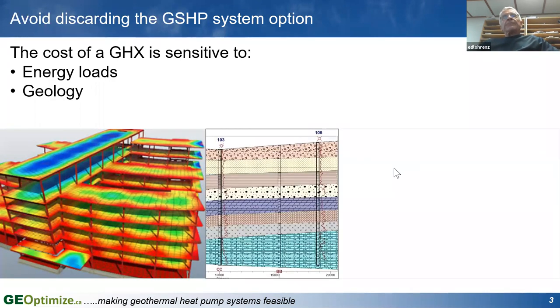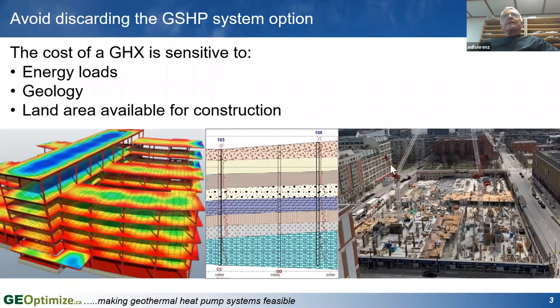The other thing that has a big impact is the geology that you're dealing with. If you're working with clay, that has a certain thermal conductivity, certain thermal properties that may limit how much heat you can put into it, which means you need to put more pipe in the ground. If you're putting pipe in something like granite or limestone or bedrock, the heat moves more readily through different types of rocks. And if there's groundwater flowing through the cracks and fractures in the limestone, that can further enhance the performance of the system.